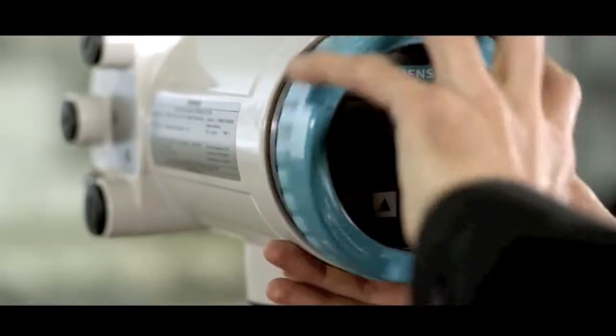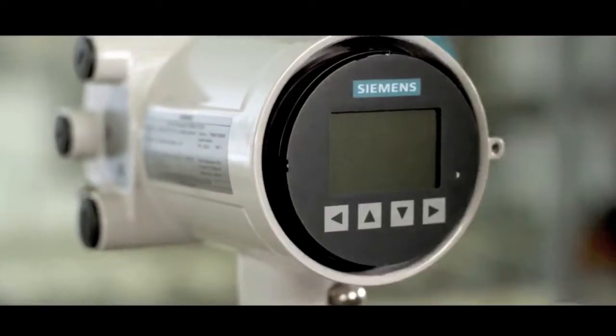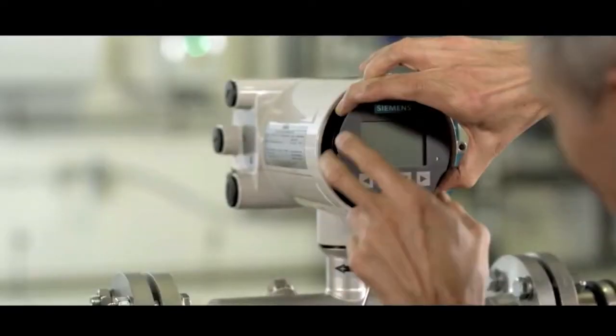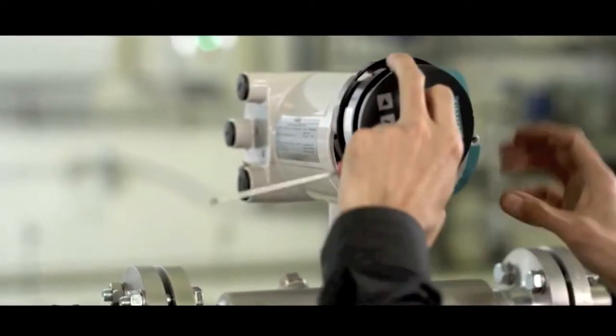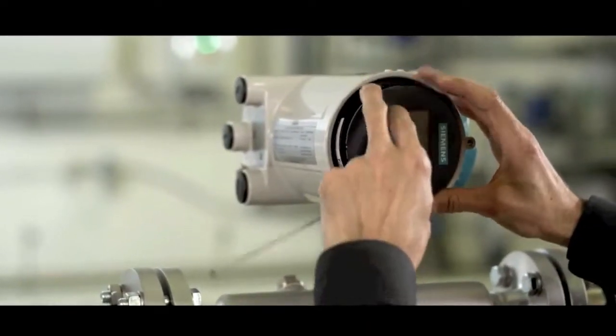The display of the transmitter can be rotated in increments of 30 degrees. Loosen the lid lock screw and remove the display cover. Carefully pull out the display, rotate it to the desired position, and gently push it back into place.